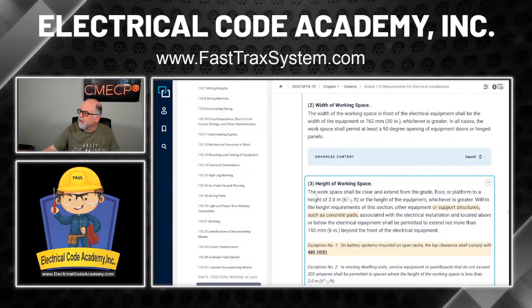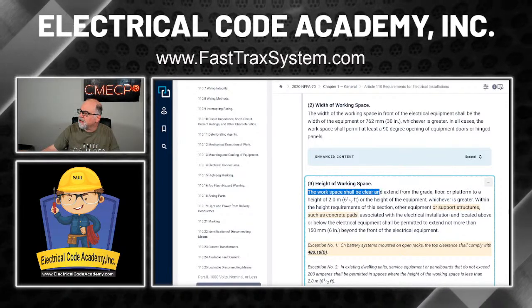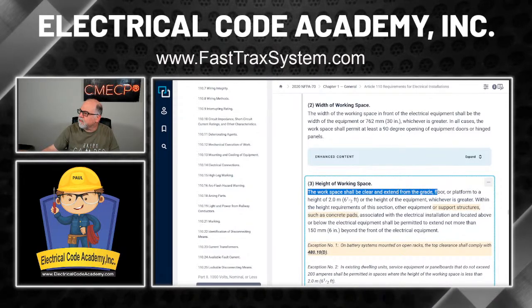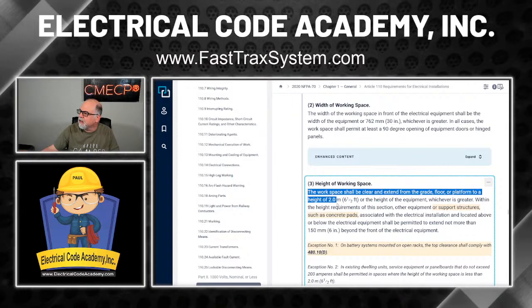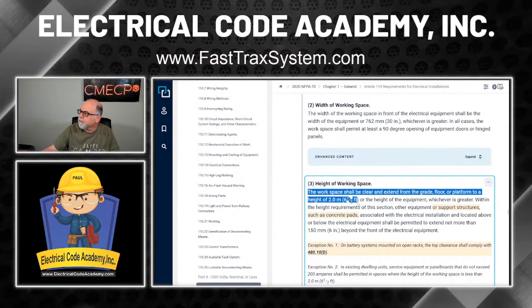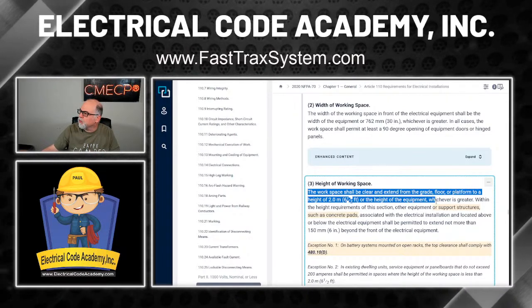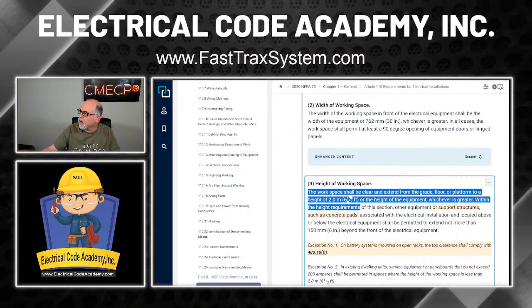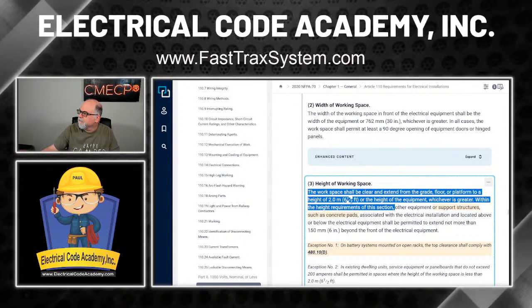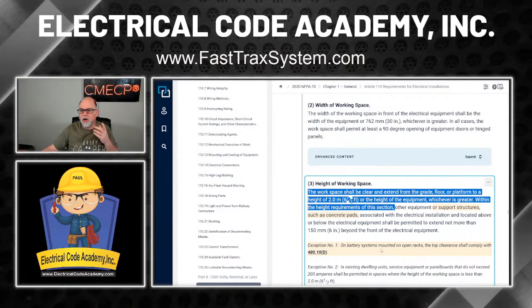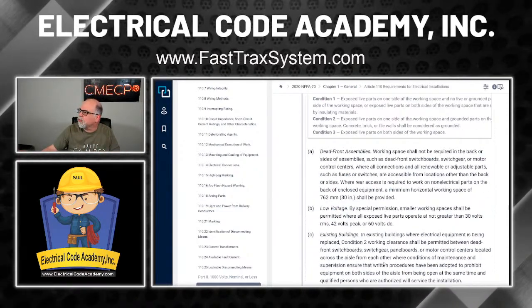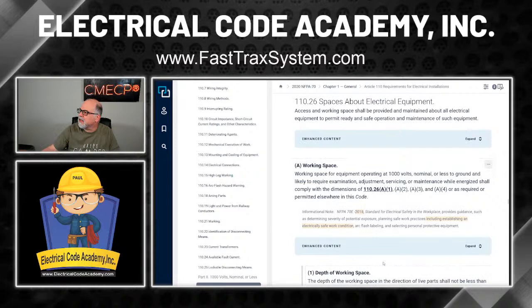Okay, it says the working space shall be clear and extend from the grade, floor, or platform to a height of 6.5 feet, or the height of the equipment, whichever is greater, within the height requirements of this section. Okay, so if you go back and look at it, and also just so we're clear, let's go back to the beginning here.